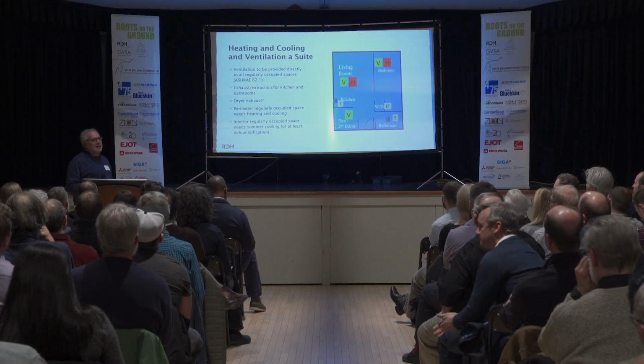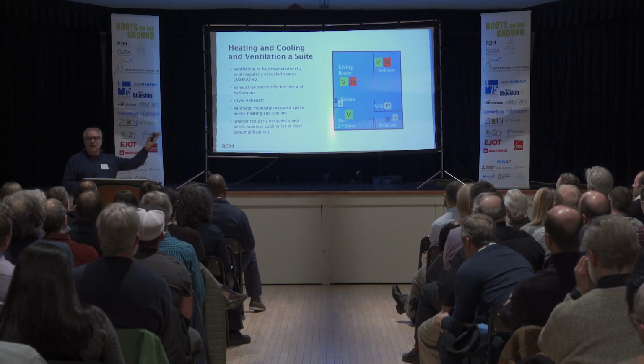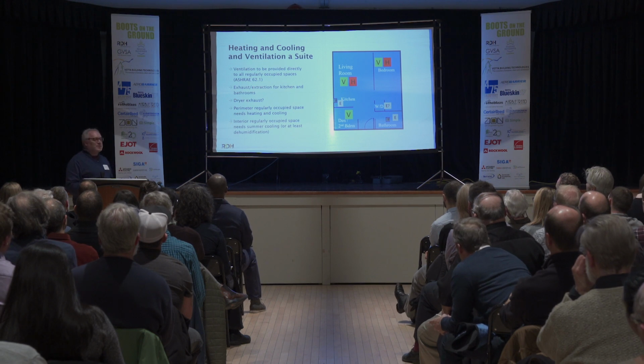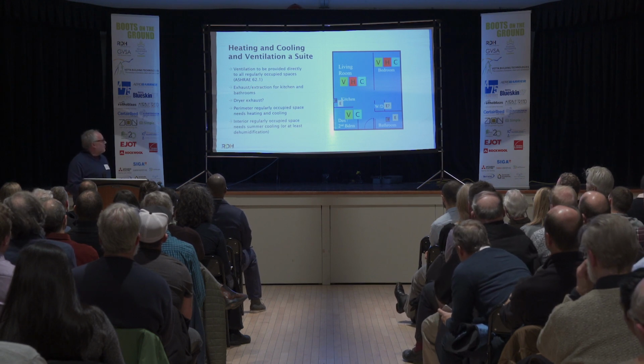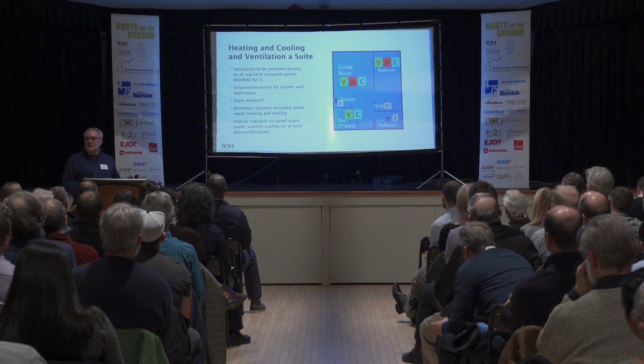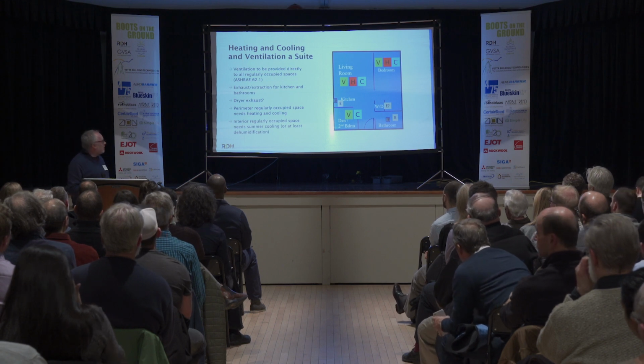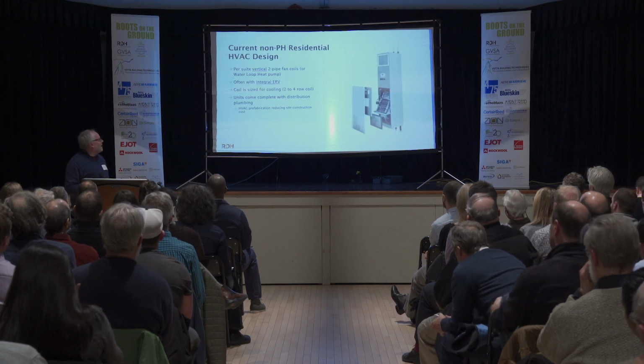Of course, we need to provide heating, typically at the perimeter. That's where the heat loss is, or at least in those perimeter spaces. And we need to provide cooling everywhere, and at least dehumidification, especially here in Southern Ontario. So that creates some challenges.